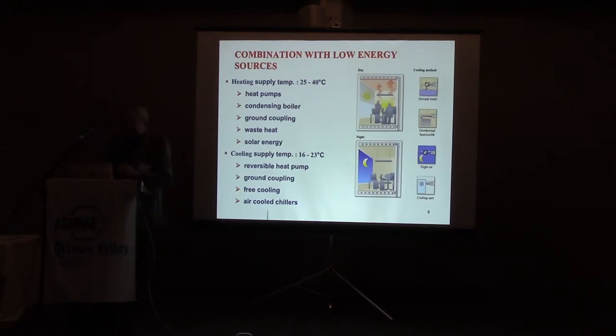So by having a temperature range which is narrower or closer to space temperature, we get higher efficiency of our systems, of our heat pumps, our COP value, condensing boiler for heating, ground coupled. We can use more of the waste heat and also solar energy. And for the cooling, again, we can use ground coupled, sometimes directly without having any heat pump in between. I'll show you some examples of that. More opportunities to use free cooling, basically to get more advantage of natural energy sources.